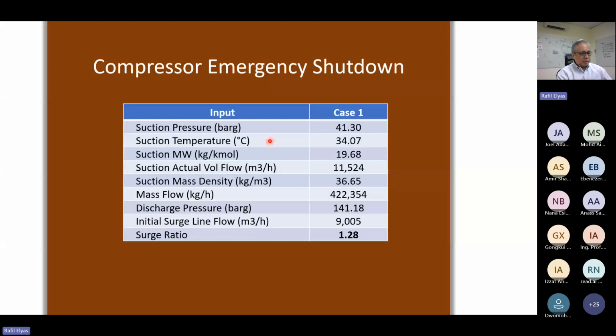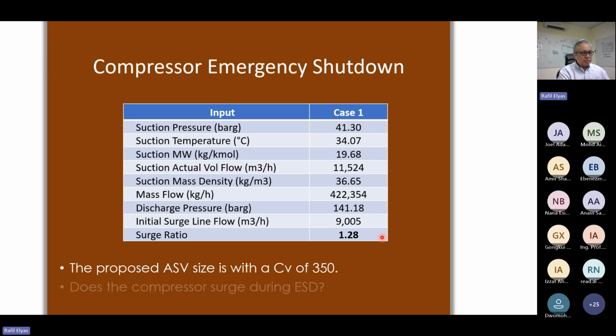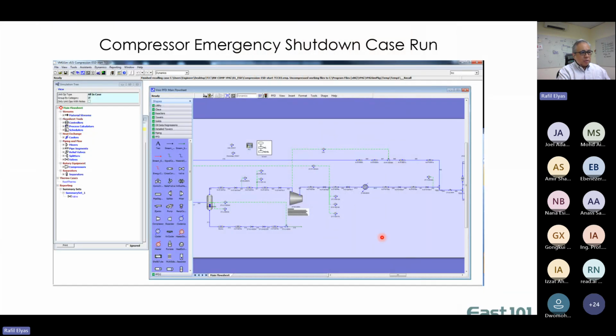I've got some of the details over here in terms of the suction conditions and the discharge conditions. Initially, the proposed ASV, anti-surge valve, size is about a CV of 350. So we want to know whether this compressor is going to surge during emergency shutdown. So this is the model. This was actually built in a software called VMG Sim, but you can use any kind of simulation tool.